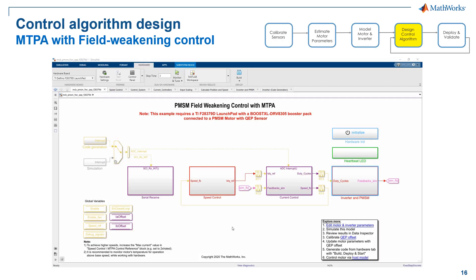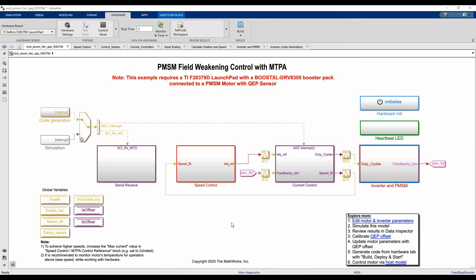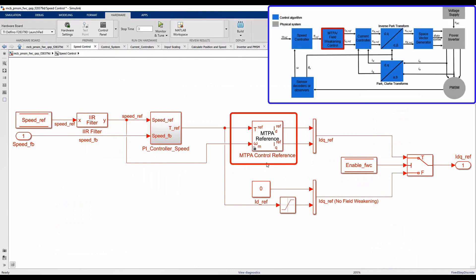Now we have an accurate plant model and are ready to design our controller. We will put together field orientation control algorithms with MTPA and field weakening capability, including sensor decoders or observers for sensorless control. Here we have our speed controller that computes IQ and ID references to track desired speed. The field weakening and MTPA control references have been implemented here, with torque and speed references as input variables.